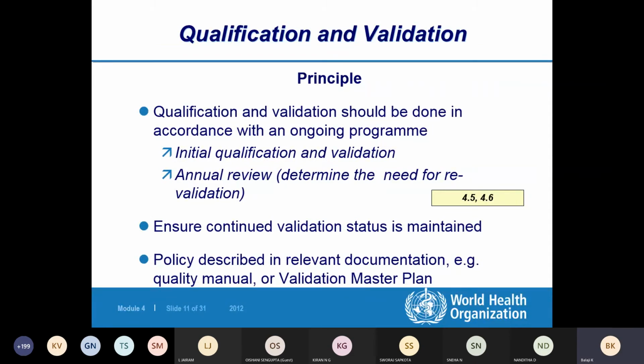So at any time the instrument should be in the validated state. There should not be any time left without validation completion. Of course, if there is maintenance, or some component is broken in the autoclave, that is fine. Once you document that a component is broken and you're waiting for the replacement, you can't even do the validation. So you have to wait till you replace the broken part, and then, if the broken part impacts product quality, you have to do a revalidation.